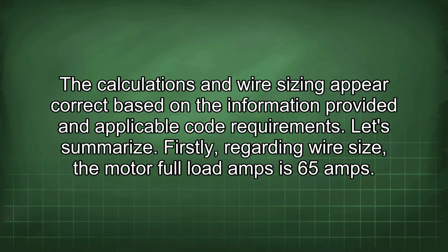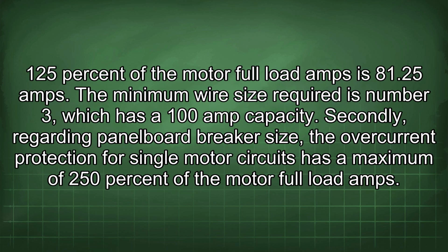Calculations and wire sizing appear correct based on the information provided and applicable code requirements. Let's summarize. Firstly, regarding wire size, the motor full load amps is 65 amps. 125% of the motor full load amps is 81.25 amps. The minimum wire size required is number 3, which has a 100 amp capacity.